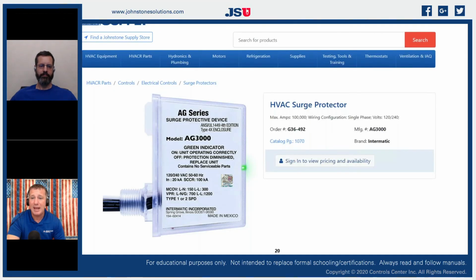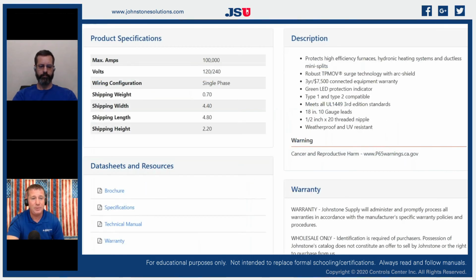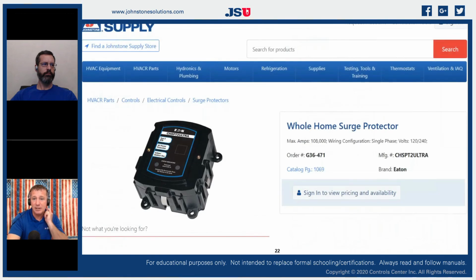So we've got the Intermatic AG3000, which is a real common surge protector. And that one's also got the MCOV control to it at 100,000 amps, 120 or 240. So pretty significant piece of equipment. The nice thing about that one is it actually offers a 3-year, $7,500 connected equipment warranty along with it. So you're adding a little bit of extra protection, and it's a great selling feature to add additional warranty or additional coverage, insurance for that installation that you're doing.